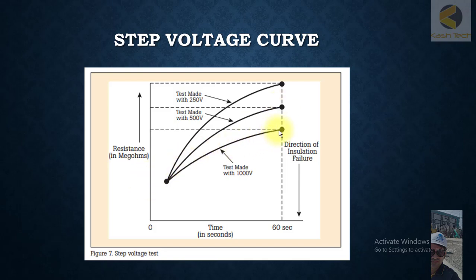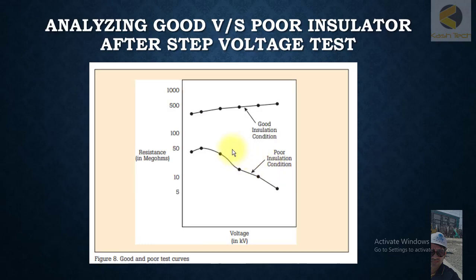The direction of insulation failure is downwards. As you increase the voltages, the mega ohms are slightly coming down. You have to basically plot the resistance in mega ohms with respect to kVs.